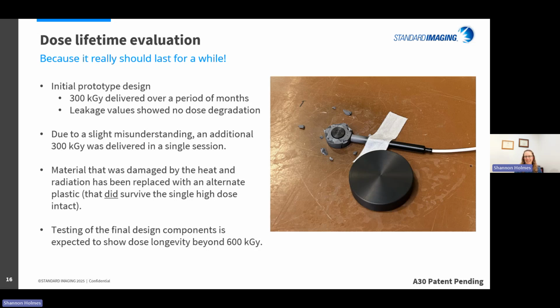And so in the later prototypes, we're replacing this particular plastic with one of the ones that did withstand that single high dose irradiation. So with the final design, we'll repeat dose lifetime testing, but we do very confidently expect that to show that these chambers should last well beyond that 600 kilogray that this one melted at.